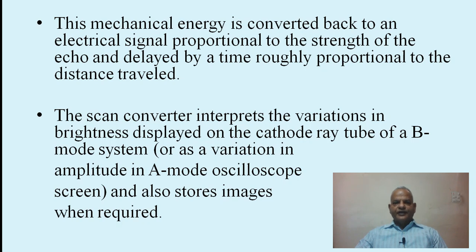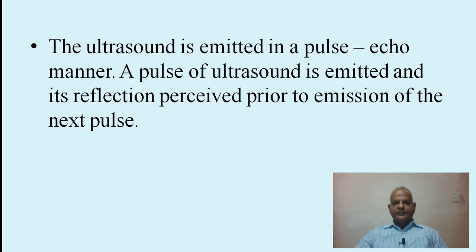The scan converter interprets the variations in brightness displayed on the cathode ray tube of a B-mode system, or as a variation in amplitude on an A-mode oscilloscope screen, and also stores images when required. The ultrasound is emitted in a pulse-echo manner — a pulse of ultrasound is emitted and its reflection perceived prior to emission of the next pulse.